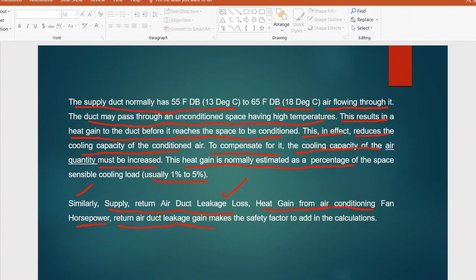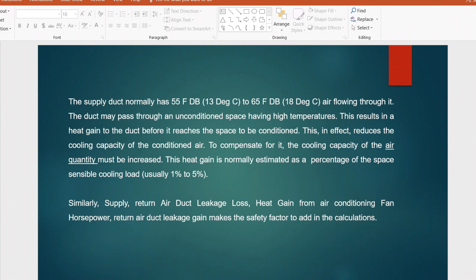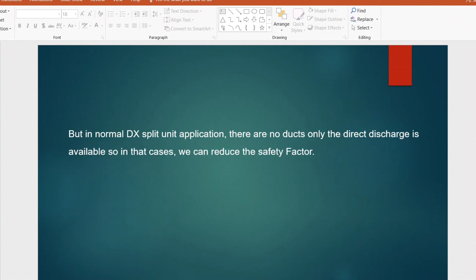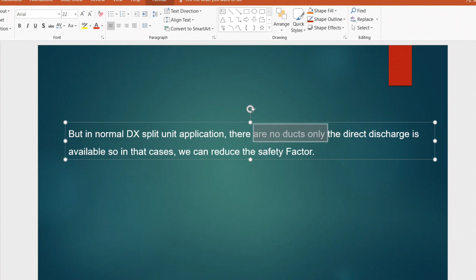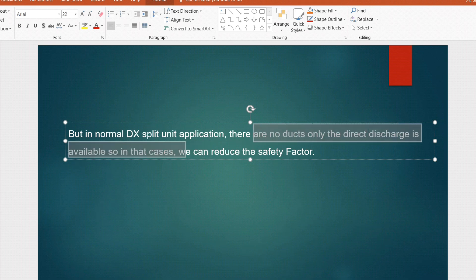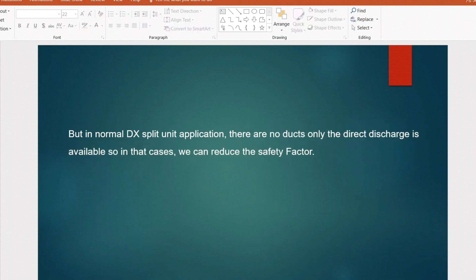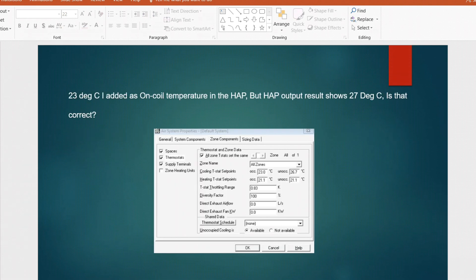Normally the safety factor is added as 10% for sensible and 5% for latent. However, for systems like a normal DX split unit installation where there are no ducts — only direct discharge — the safety factor can be reduced. There is no need to keep a 10% sensible and 5% latent safety factor for applications where there is no ductwork.